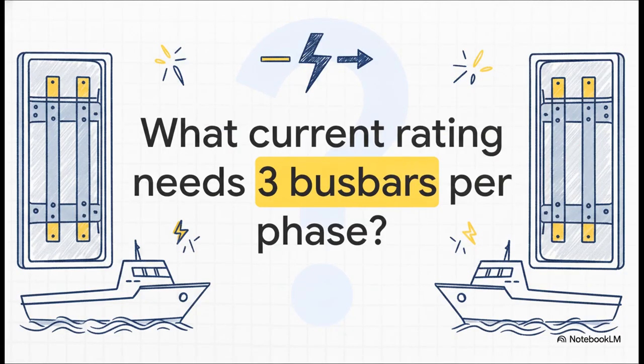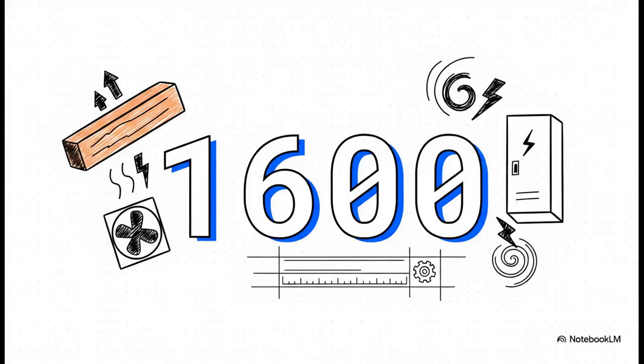So let's do a quick knowledge check here to see this in action. Imagine you're reviewing a spec sheet for a new vessel, or maybe you're out doing a physical inspection, and you look into that main compartment and count exactly 3 bus bars per phase. Based on the scaling rule we just talked about, what current rating does that physical setup suggest? If you said 1600, you hit the nail on the head. 1600 amps or higher. That extra copper bar isn't just for show, it's there for a very specific thermal reason, carrying that heavier current so the system doesn't overheat under load. Understanding this little detail lets you read the physical hardware almost like you're reading a blueprint.